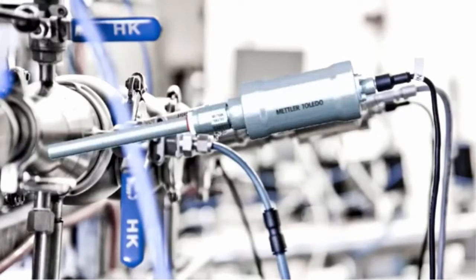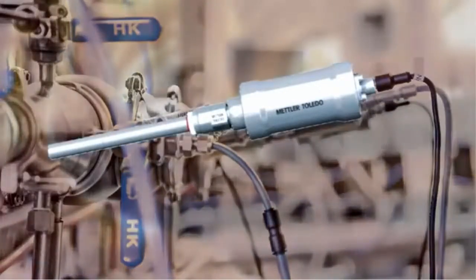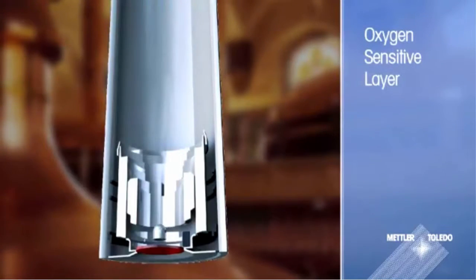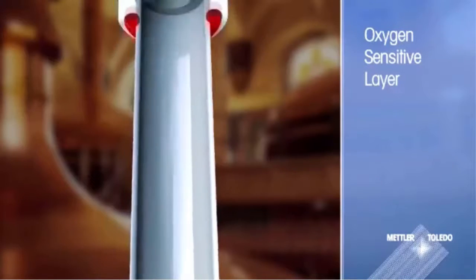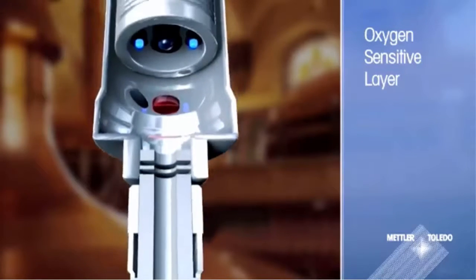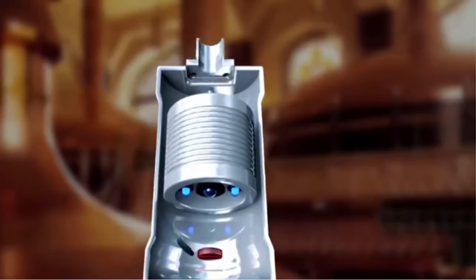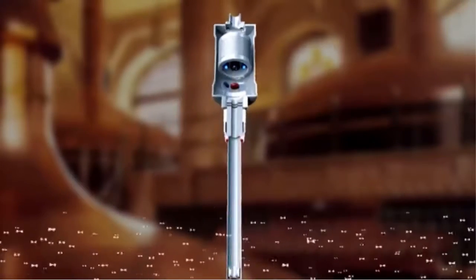Unlike most dissolved oxygen sensors available, the InPro 6970i uses a clever optical technique for measuring oxygen. At the tip of the sensor, there is a layer of molecules that absorb and emit light. These molecules are sensitive to oxygen, which alters how they behave. The greater the quantity of oxygen, the greater the changes in their behaviour.